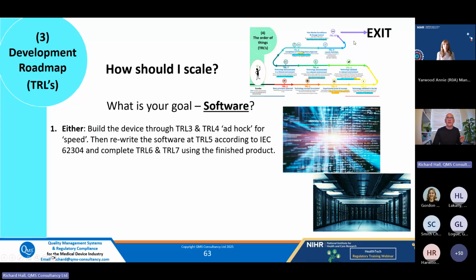to get there, you can either create software ad hoc to the end of TRL 4, and then in TRL 5, rewrite the software according to the IEC 62304 standard, and then continue by doing safety testing for interference and cybersecurity, and then do a clinical performance study with the new software to gain CE mark.